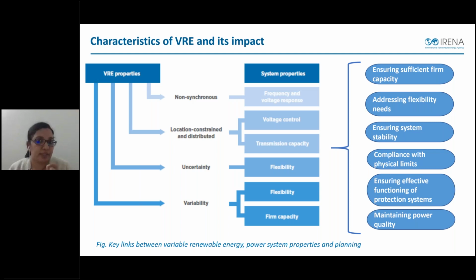They also must be very specific, like Mr. Matthias mentioned, about the stability of the system, which is a major technical concern when integrating high shares of VRE in the power system. Also, compliance with the physical limits of the system, like the thermal capacity of lines, transformers, and other network elements. Some of the grids are not designed for reverse power flows or backflows, so everything involved in accepting power generation from VRE should be reviewed. Another very crucial aspect is the effective functioning of protection systems. Because VRE is connected through power electronic devices, it doesn't contribute to the short circuit current, and because of this the protection systems don't function effectively. So there is a need for reviewing the protection system settings. Next slide, please.